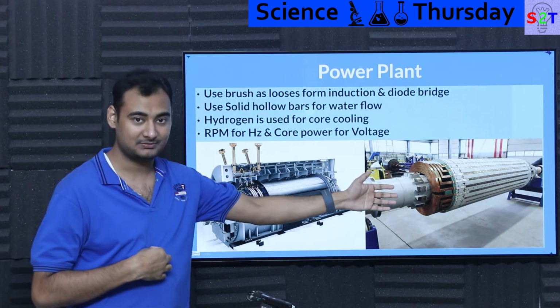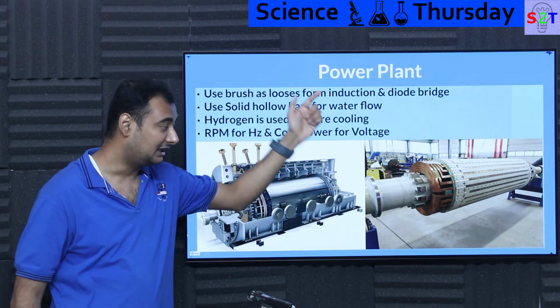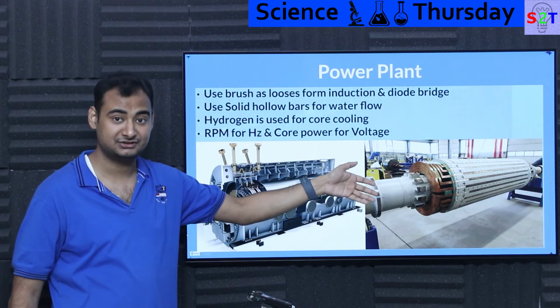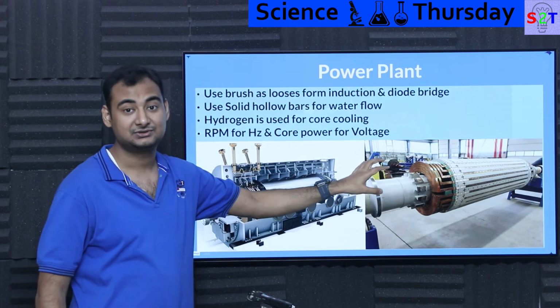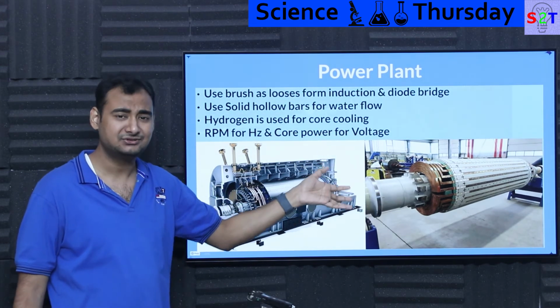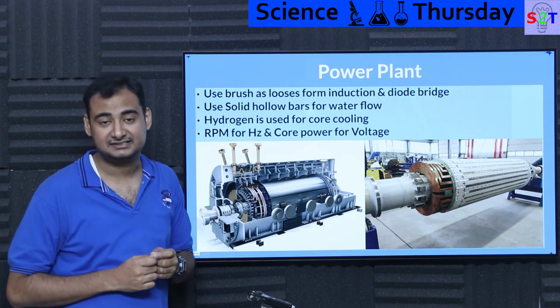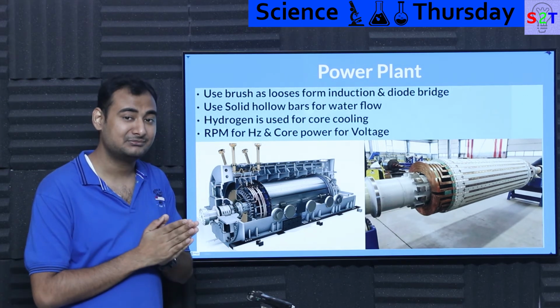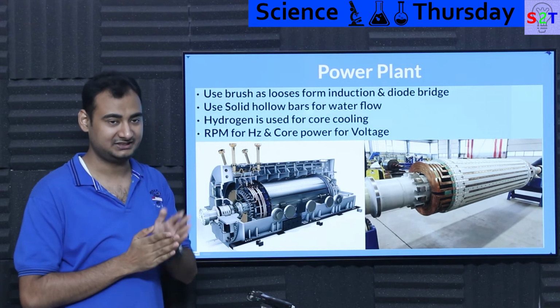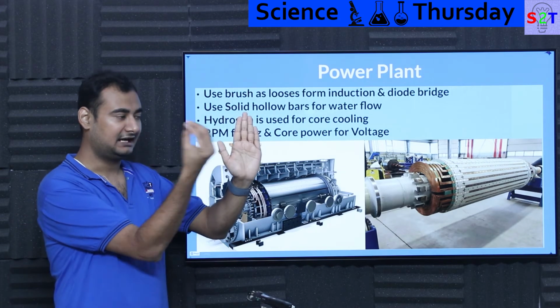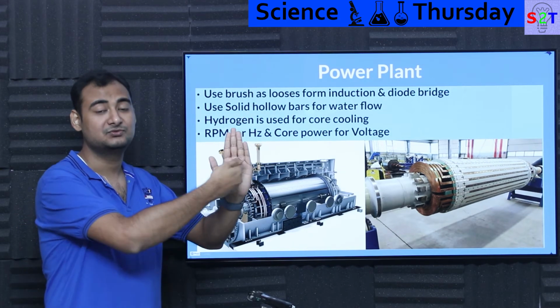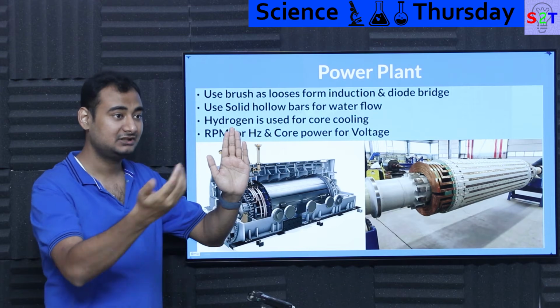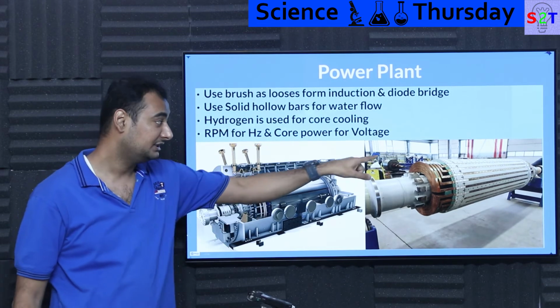Then we come to the rotor part. Again, this is also an electromagnet. How the heck do you want to keep this cool, with megawatts of energy going into it? So what people utilize is hydrogen. Now, wait a minute, hydrogen, why? Well, hydrogen is the lightest gas. What does that mean? That simply means at any given temperature, it has the highest movement speed, meaning when hydrogen collides with a hot surface, it moves at much higher velocity, it creates much more turbulence, and it extracts more energy from the hot surface, so it cools it down.